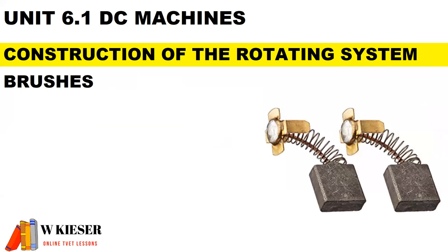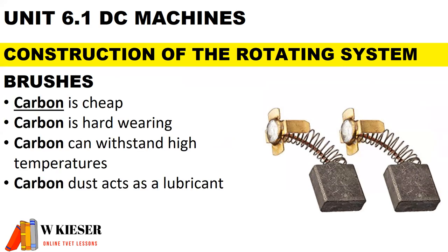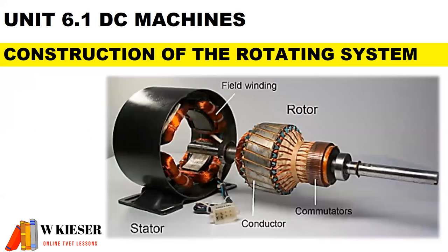For brushes, there are two main types: carbon and graphite. For carbon brushes, the reason why manufacturers like to use carbon is that carbon is cheap, hard wearing, it can withstand high temperatures, and the dust acts as a lubricant.